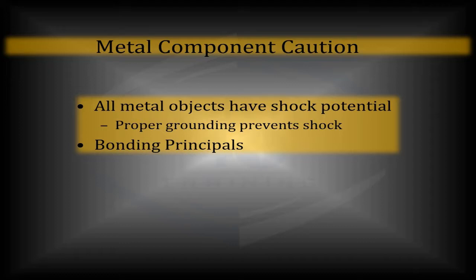It's important to realize that it is code and it is enforced in most areas. However, code officials will enforce this in a little bit different way in different areas. So make sure you understand what they want. And in most areas, guess what? Mechanical guys can't do it. Not physically can't do it, but by licensing reasons, they can't do it because they can't terminate that bonding wire properly because it's going to be inside of that panel.